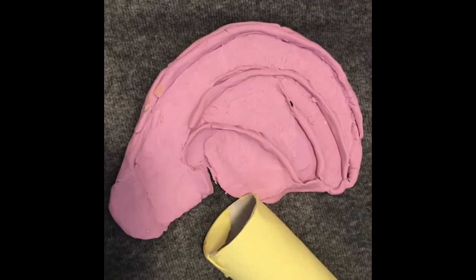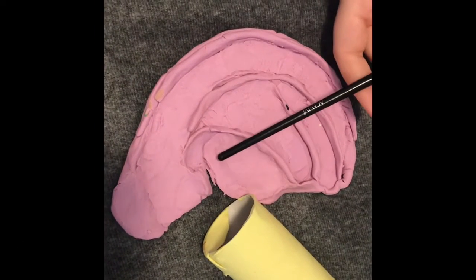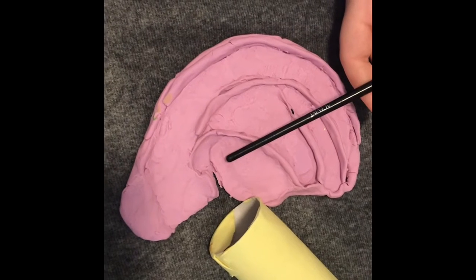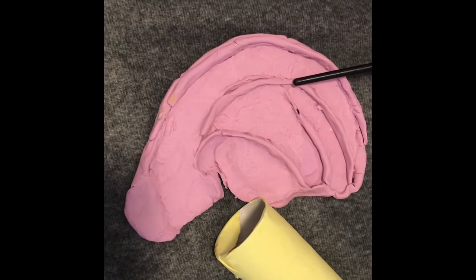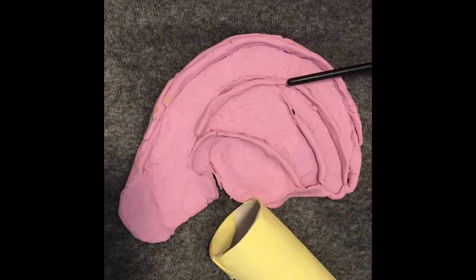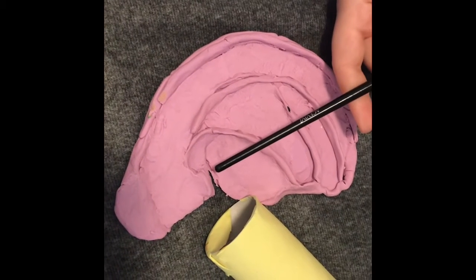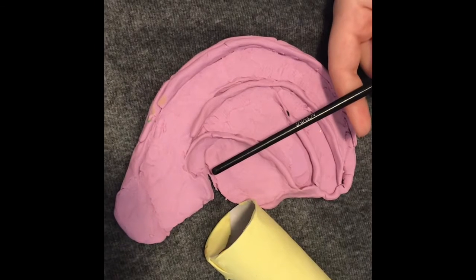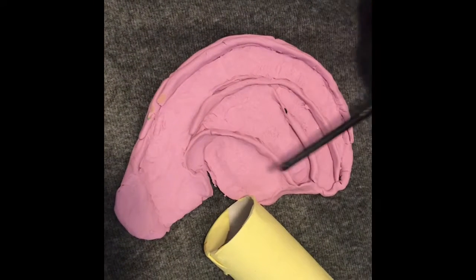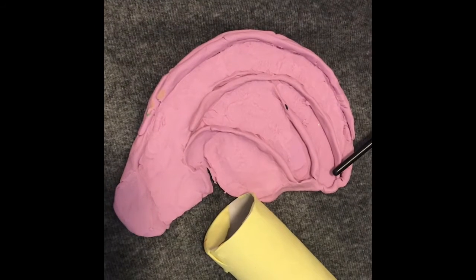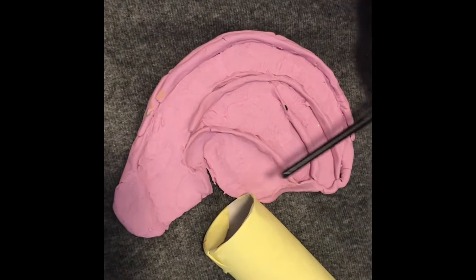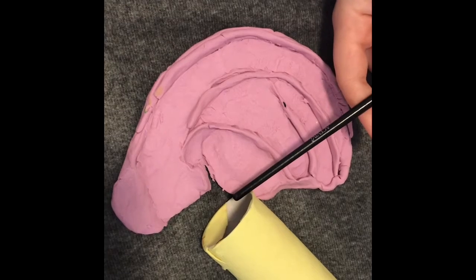Going farther in depth, the concha, which is the bowl of the pinna, is important for ear molds and custom hearing aids. The antihelix provides retention for custom hearing aids and ear molds. The antitragus provides retention and helps determine the size or feature restrictions with custom hearing aids. The crus of the helix helps with retention of full shell ear molds and hearing aids. The tragus helps retention with ITCs and can hinder the size of hearing aids.